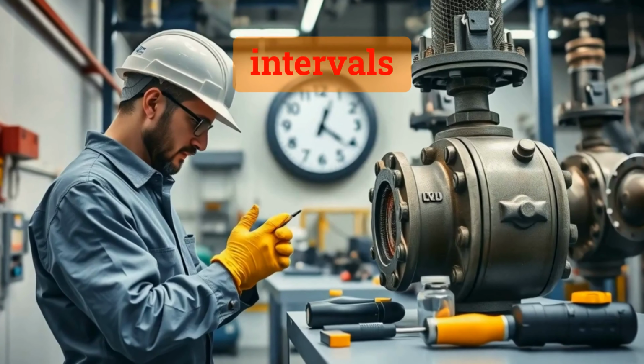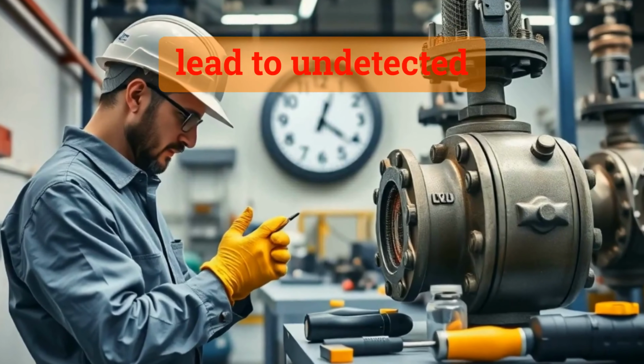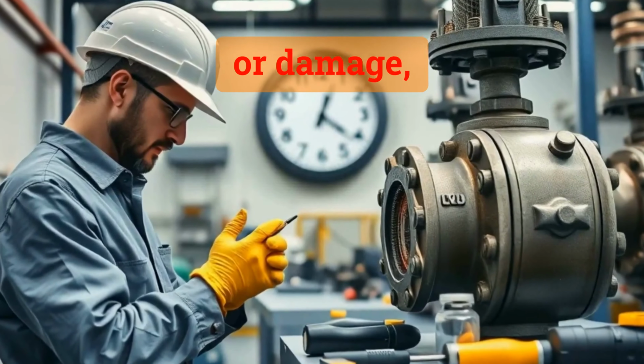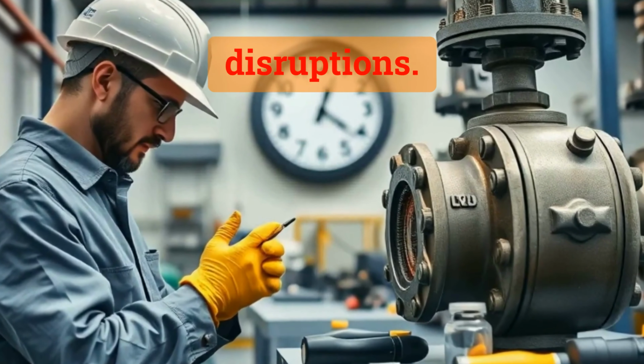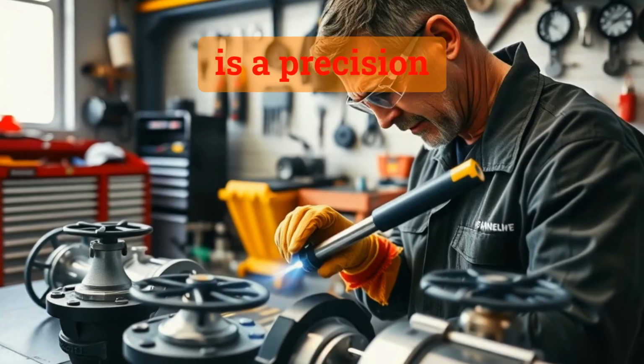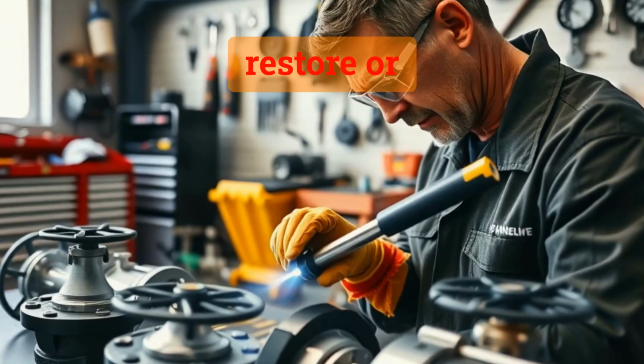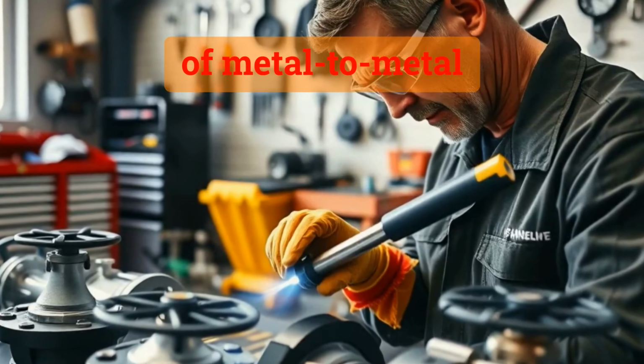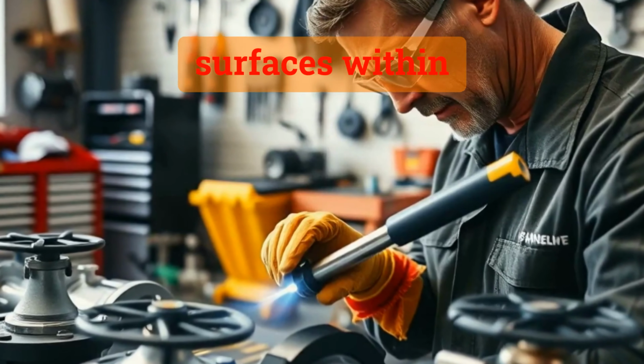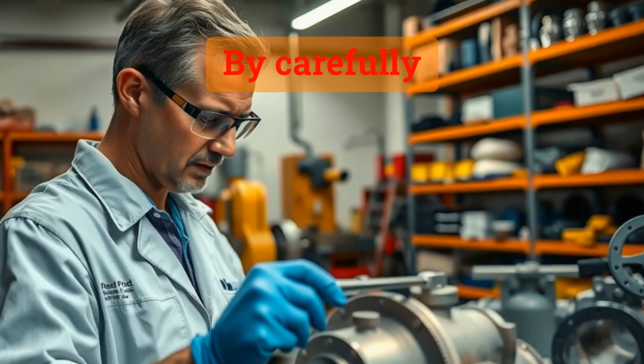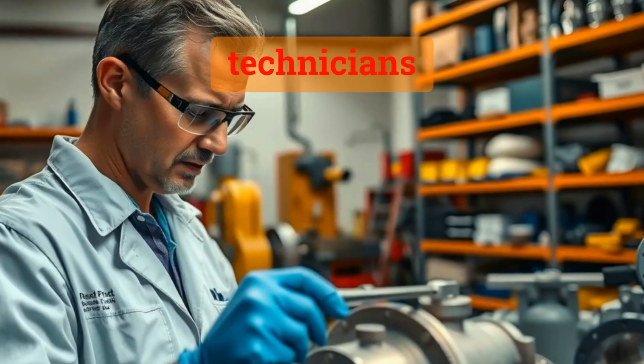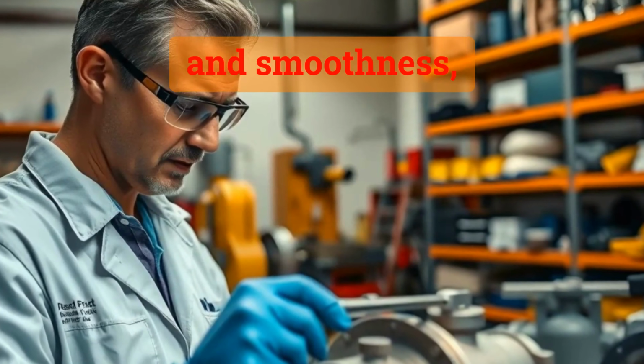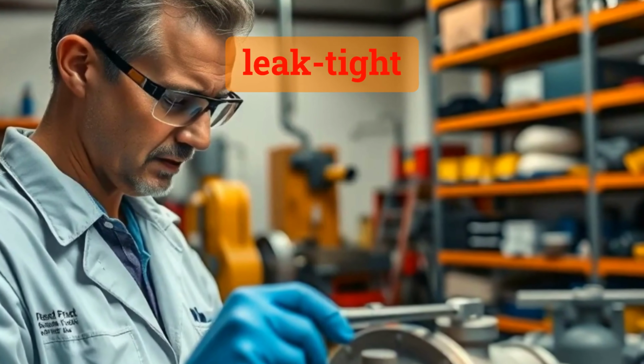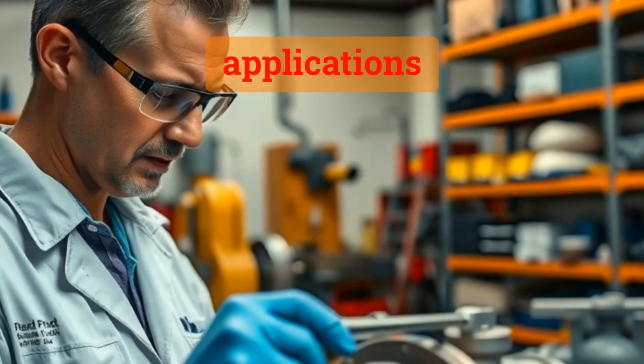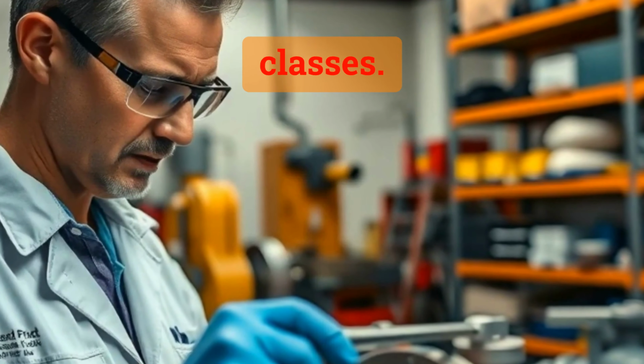Extending maintenance intervals without proper diagnostics can lead to undetected wear or damage, increasing the risk of operational disruptions. Sealing surface lapping is a precision finishing process used to restore or enhance the tightness of metal-to-metal sealing surfaces within a valve. By carefully lapping these surfaces, technicians can achieve a high level of flatness and smoothness, ensuring leak-tight shutoff even in demanding applications that require stringent shutoff classes.